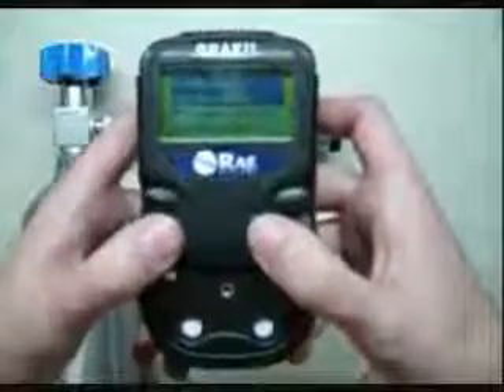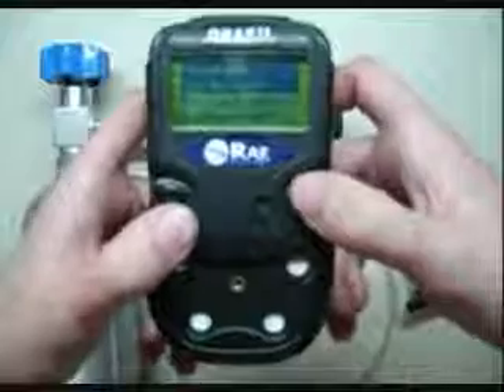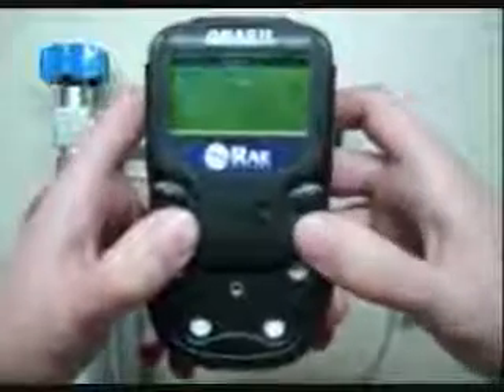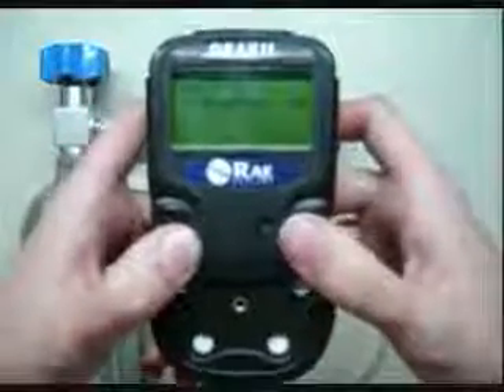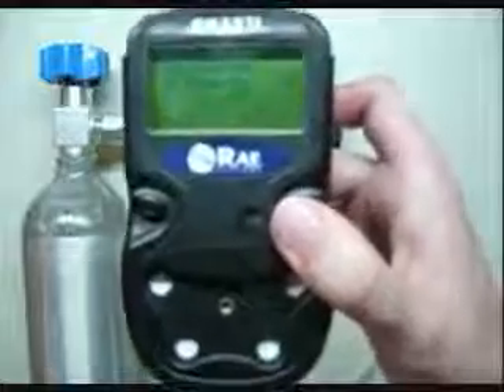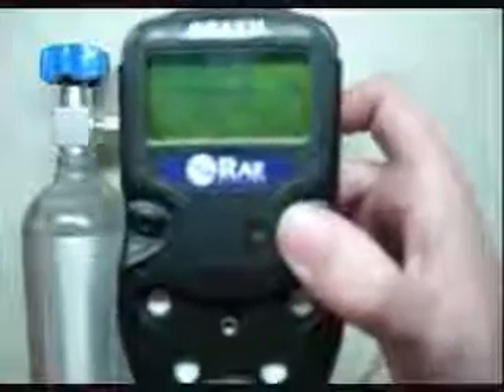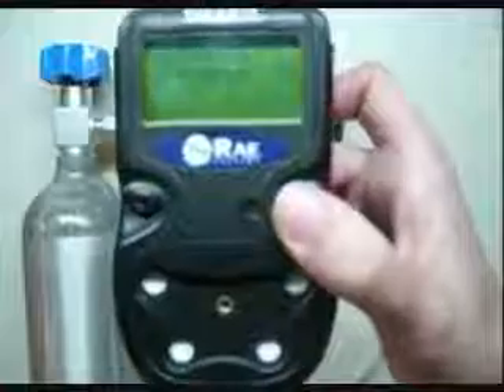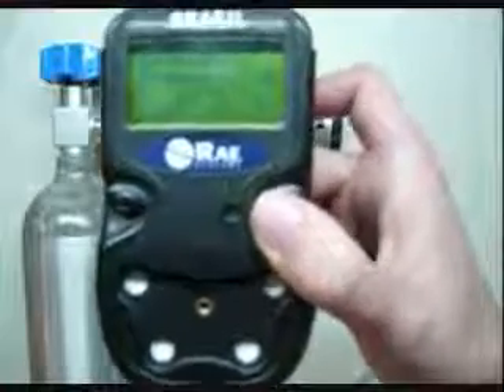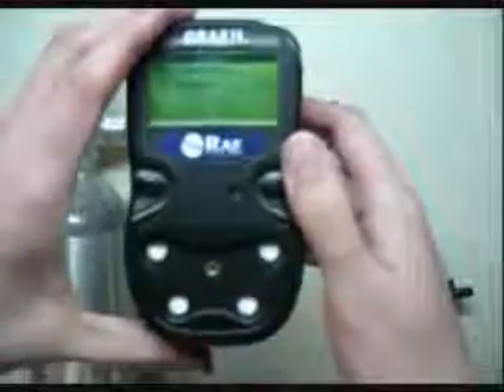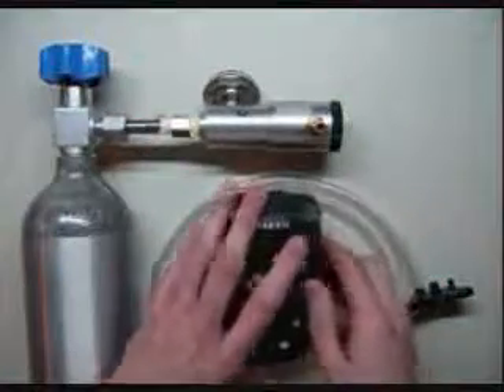and it'll ask if you want a fresh air calibration. Always start with a 0. It's just good practice. Occasionally, if you have lingering calibration gas in there, and you hit 0, it'll zero at a point at which there's still some gas in there that you've forgotten about. I'm going to go through a calibration for the 0 point. It takes about 30 seconds. Let's put it down for a minute.